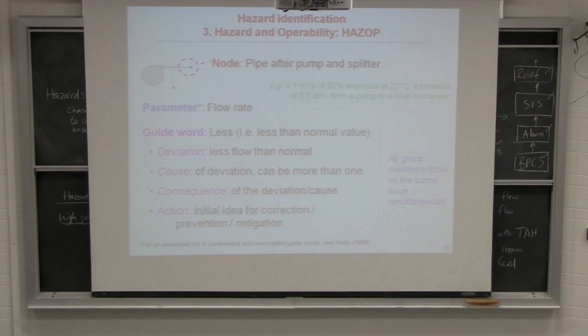And this is where the whole group of people start to creatively look at the process and say, what could be the cause of lower than normal flow? And as the chemical engineer, you might isolate the pump as one example. That the coupling between the motor and the pump is broken, so the pump is actually not providing the flow required. Or a blockage in the pipe that's providing lower than normal flow. Other people there might have different ideas for the cause.